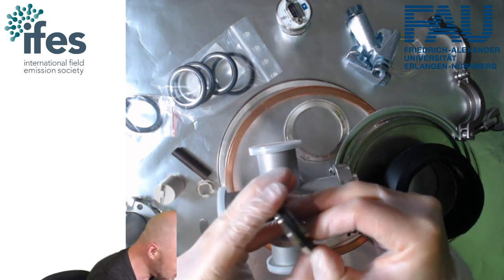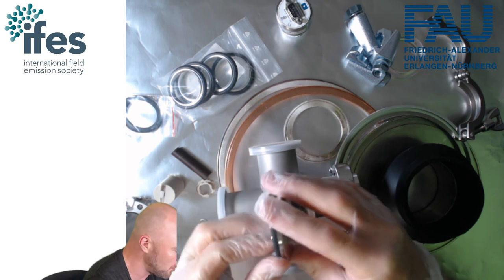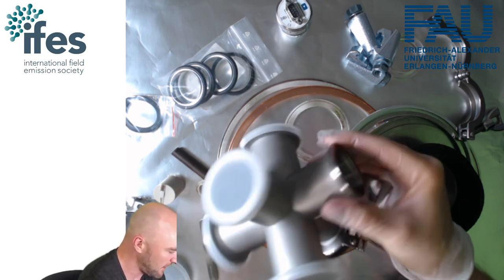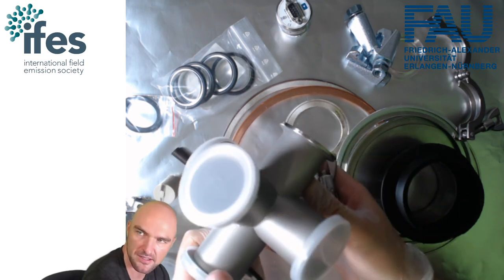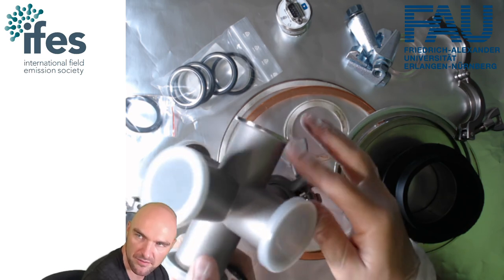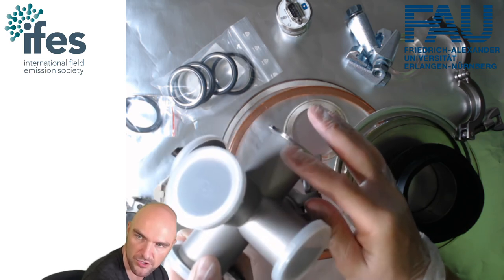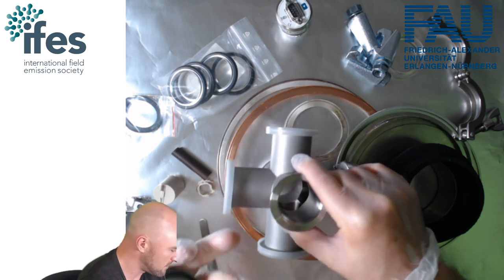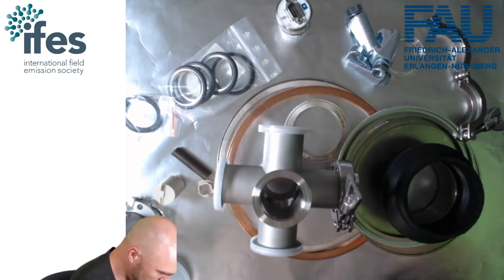Anyway, so ISO KF flanges are what you will see a lot with your pumps. ISO KF flanges are essentially conical flanges. So you can see here at the flange where we have a little bit of a cone shape.